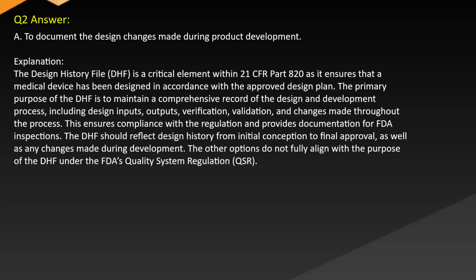Answer. A. To document the design changes made during product development. Explanation. The design history file, DHF, is a critical element within 21 CFR Part 820, as it ensures that a medical device has been designed in accordance with the approved design plan. The primary purpose of the DHF is to maintain a comprehensive record of the design and development process, including design inputs, outputs, validation, and changes made throughout the process.